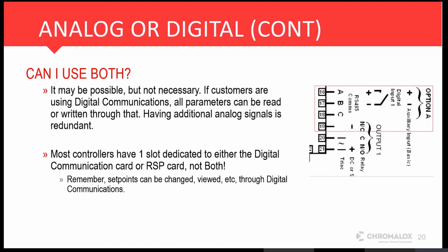And then also a lot of the controllers, they use the same slot. So you can see on the right-hand side there, that's just a snapshot, I think, of the 40 series controller. Pin 16, 17, 18, that's the RS-485 Modbus card. You can see that's also where the remote set point card would go. So if you're using one, you can't use the other one. So again, if you're using the Modbus, you can probably just handle everything through that.